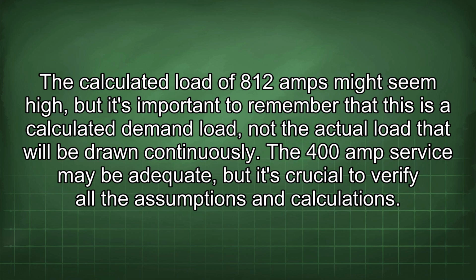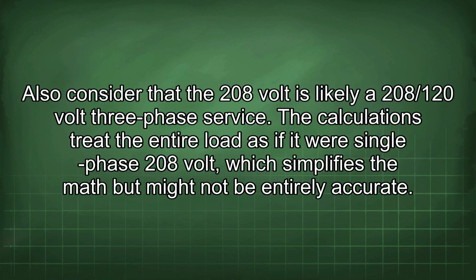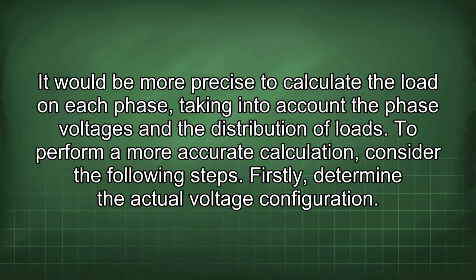The 400 amp service may be adequate, but it's crucial to verify all the assumptions and calculations. Also consider that the 208 volt is likely a 208/120 volt three-phase service. The calculations treat the entire load as if it was single-phase 208 volt, which simplifies the math but might not be entirely accurate. It would be more precise to calculate the load on each phase, taking into account the phase voltages and the distribution of loads. To perform a more accurate calculation, consider the following steps.